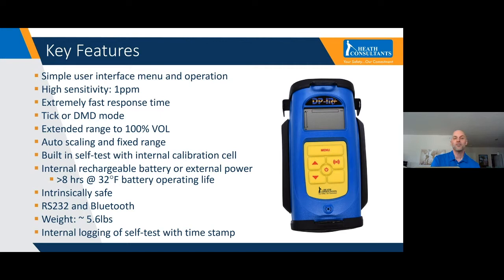There's a built-in self-test with it. So I mentioned we do recommend doing the self-test once a day. Everything you need to do that is built right into the instrument itself. So there's a little calibration cell in that. So there's nothing external, no other gases or bottles or tubing that you need for that. Everything is contained right in the instrument to perform that self-test. It's a rechargeable battery. You generally get 8, 9, 10 hours, so a full day of operation, no problem with the battery on the unit.